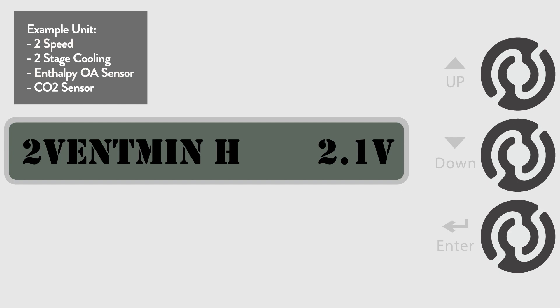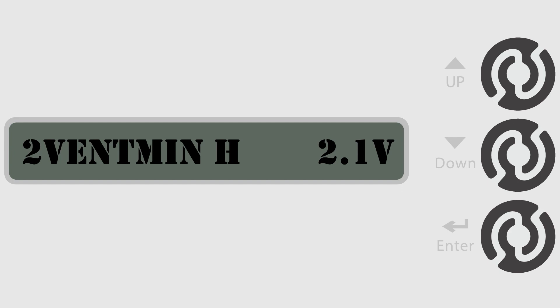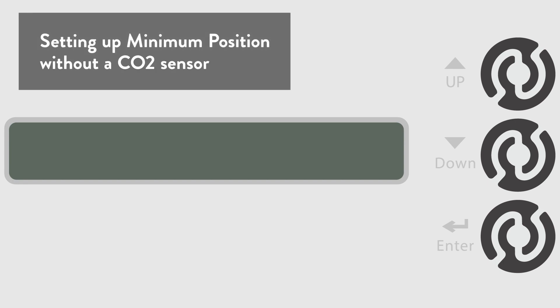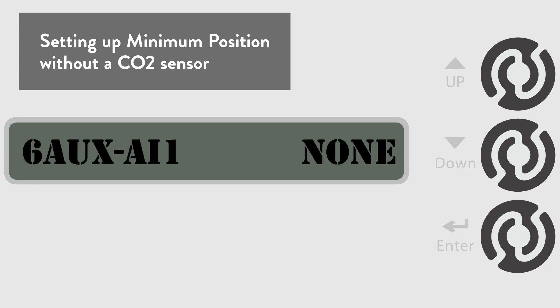Our objective of setting up a 2-speed unit with 2-stage cooling using an enthalpy outside air sensor and a CO2 sensor is now complete. However, there are a few typical settings to review. If we didn't have a CO2 sensor, the 6 AUX AI1 menu would need to be set to its default of none. In this case, we could just adjust the minimum position settings. You can leave these at the default settings or make changes, which we will do. In this example, we are still using a 2-speed unit, so we will have to adjust the low and high speed settings in the 8 run state menu.